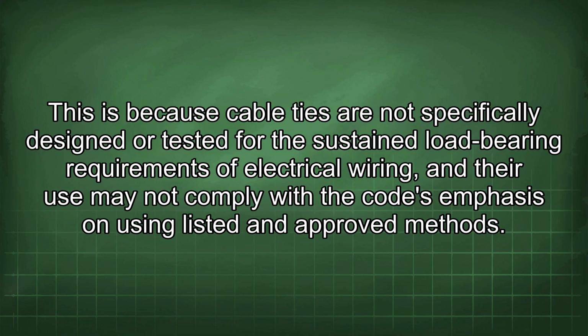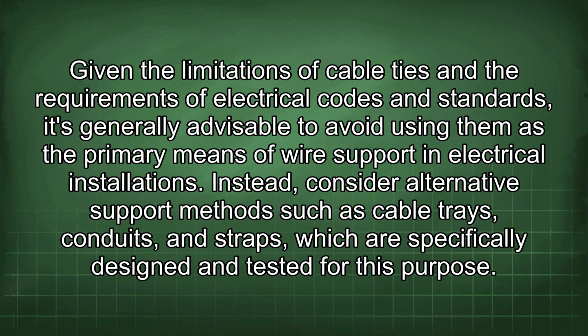This is because cable ties are not specifically designed or tested for the sustained load-bearing requirements of electrical wiring, and their use may not comply with the code's emphasis on using listed and approved methods. Given the limitations of cable ties and the requirements of electrical codes and standards, it's generally advisable to avoid using them as the primary means of wire support in electrical installations.